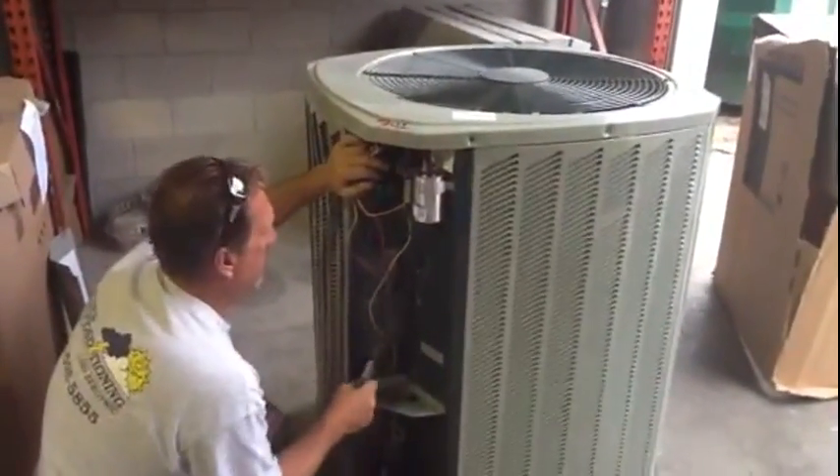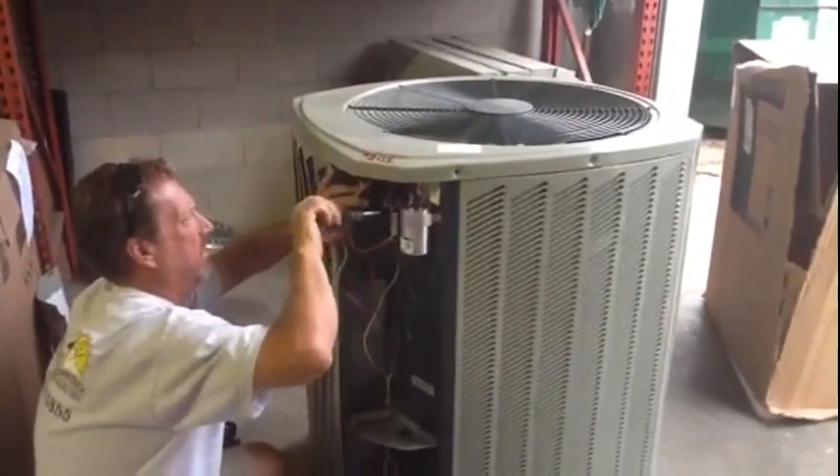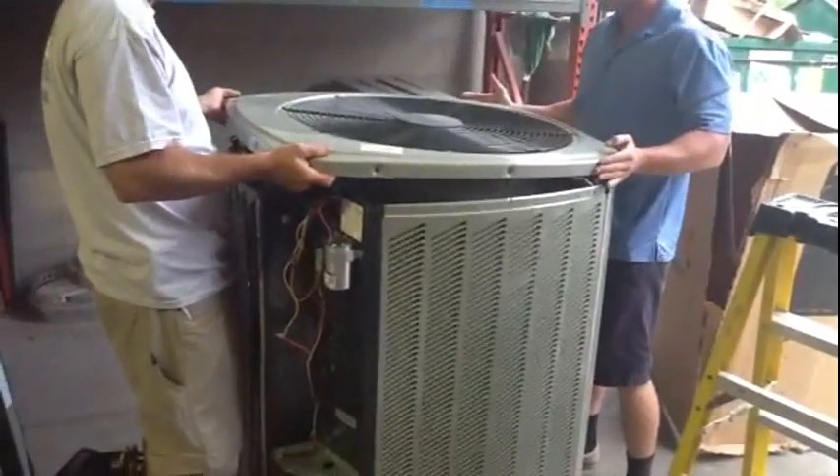This morning what we're going to do is replace the compressor in this Trane unit. He's taking all the screws out of the top of the condenser and he is going to unhook the wiring coming from the condenser motor. We're taking the top off this condensing unit now to expose the compressor that we're going to replace. Here is the Trane Climatuff compressor that we're going to take out. Now we're going to grab these pipe wrenches because these things have rotolocks on the condenser compressor and Art's going to go ahead and start taking those apart.